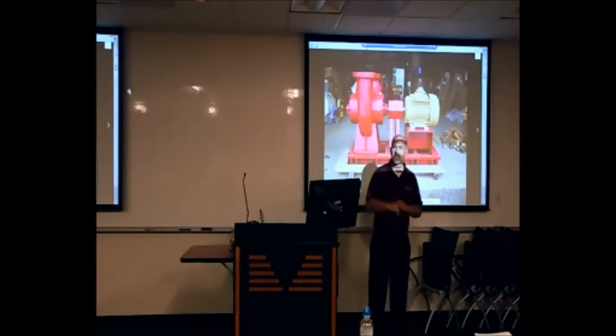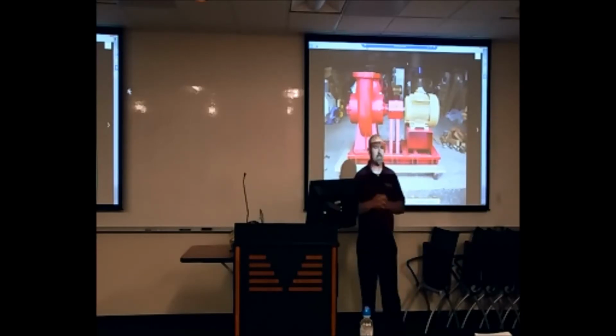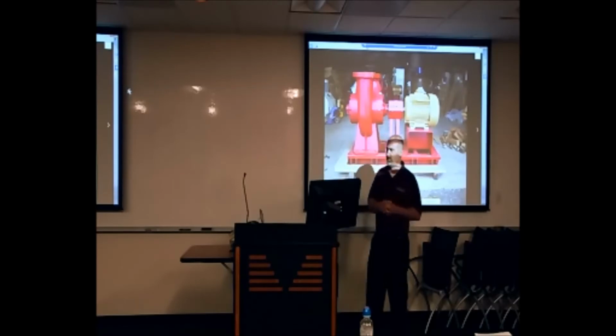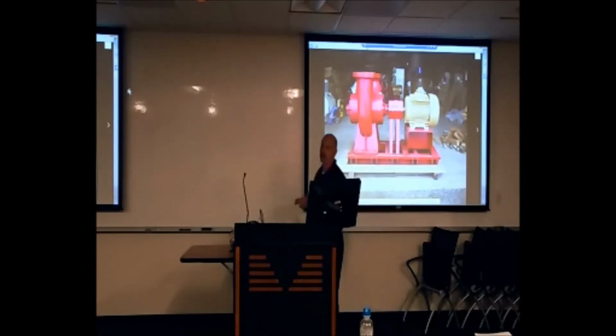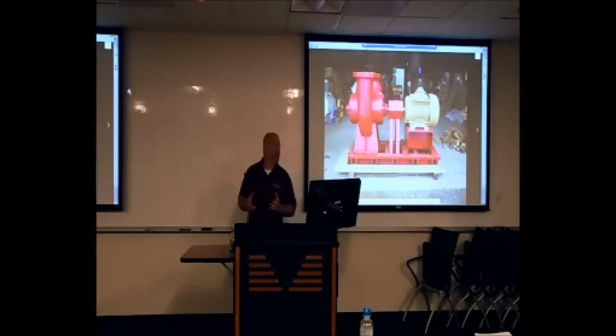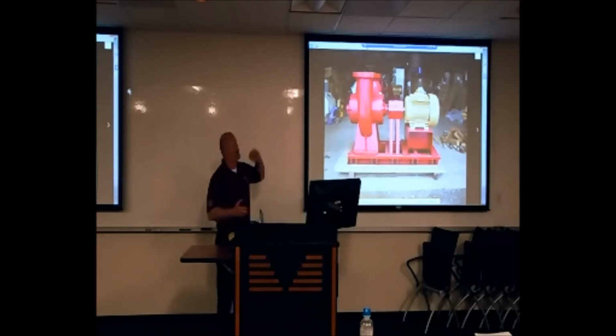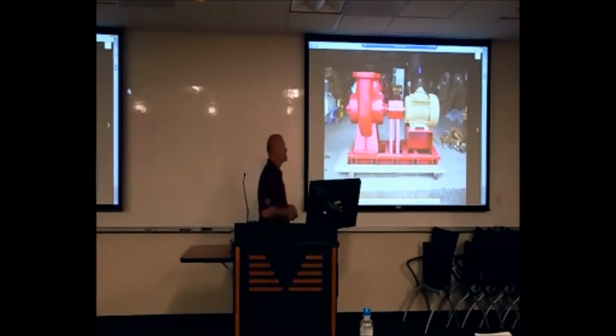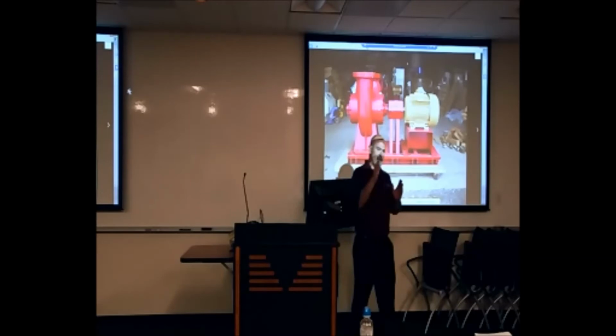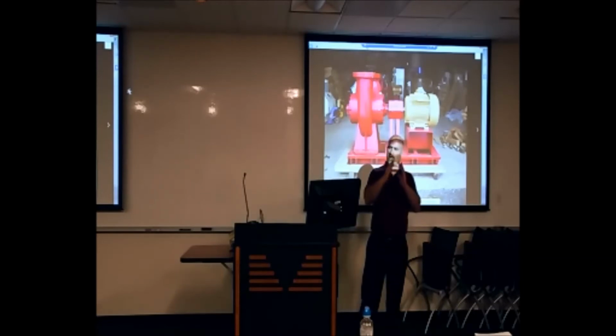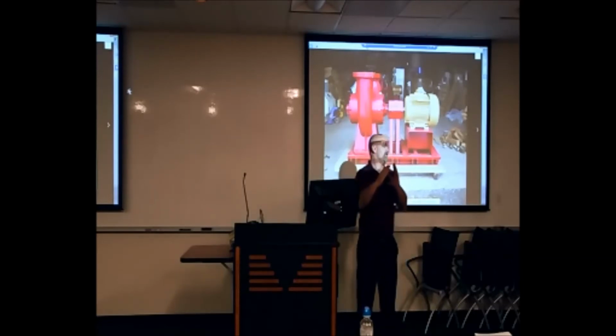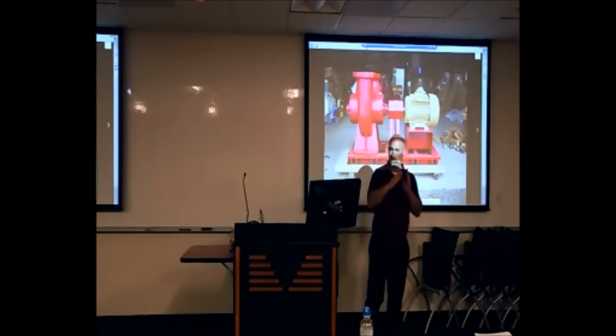One of the things I wanted to discuss, though, that's specific to this project is NPSH. Some people think NPSH stands for not pumping so hot. NPSH is actually net positive suction head. These pumps have a requirement of pressure to come into the inlet of the pump. When I run the calculations, it's about 2.5 to 3 pounds. On the gauge when I was out there the other week, I noticed that it was hovering somewhere between 0 and 1 pound. So it's very, very low.